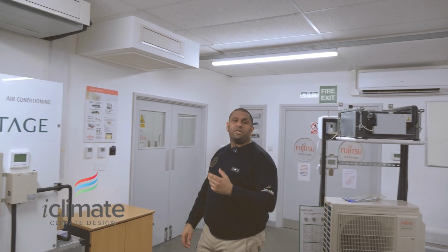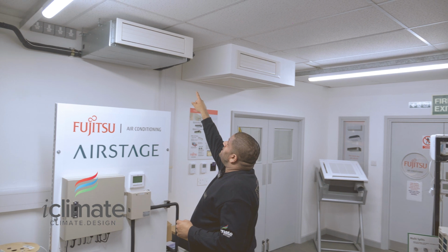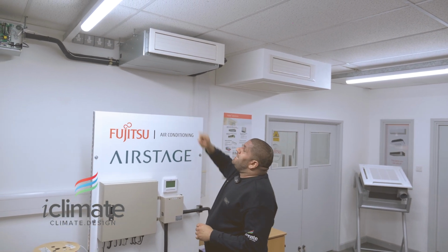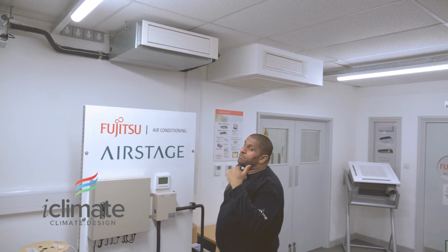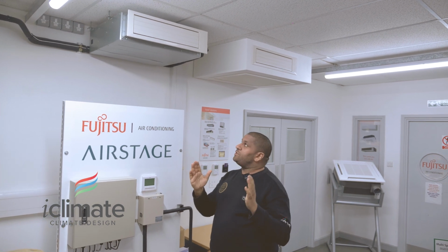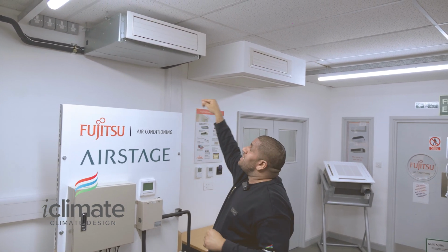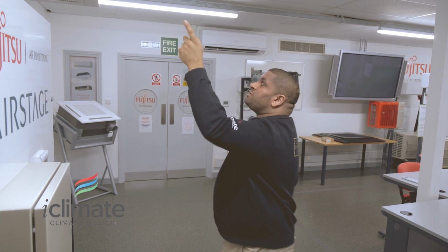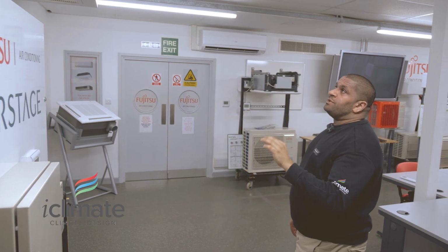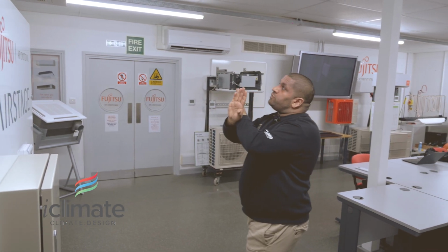Right, finishing off with the concealed air conditioning, if you have a look up here, this is a slim ducted AC unit. It's different from the one that I showed you that is applicable to the wardrobes. That is a smaller compact unit. This is a typical ducted unit designed to go within a ceiling. It has an automated grill on the front of this unit, which is very cool. So essentially, when it's closed, the grill louvers will be flat.